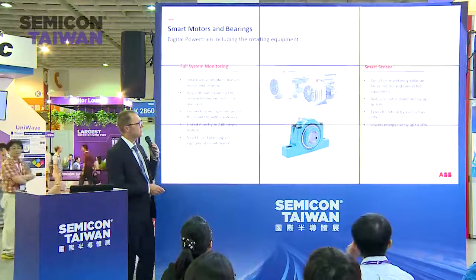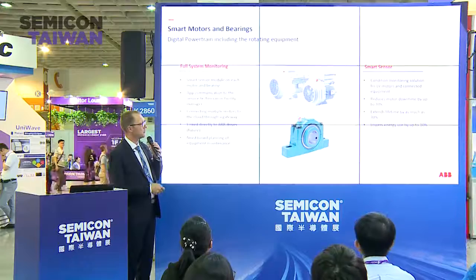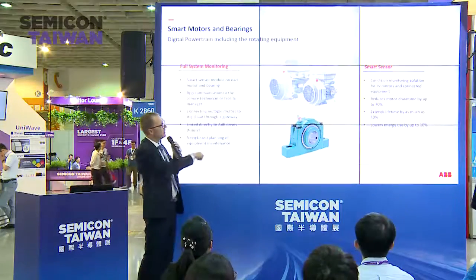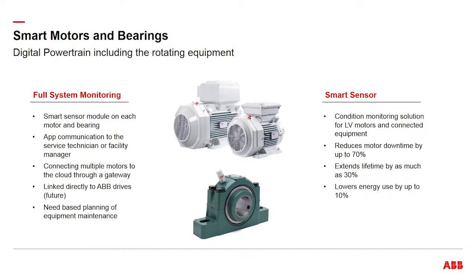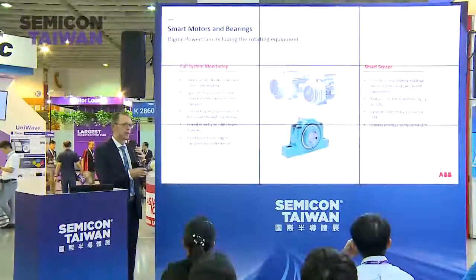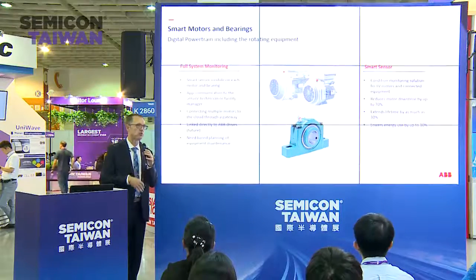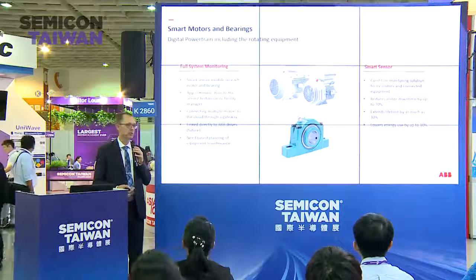I mentioned we also have sensors on our pumping or motor equipment and our gears, so you can see them here. What's traditionally been a dumb piece of equipment, just mechanics and metal, now has a bit of electronics added so we can capture data for analysis. That allows app communication too, so your local tech can see bearing temperature, vibrations, and we can connect multiple motors into a gateway solution, or in the future directly into the drives, since the new generation of drives have embedded Bluetooth capability.